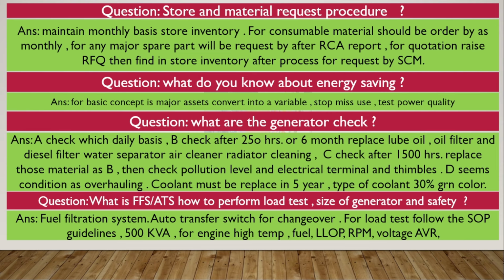What is FFS, ATS, how to perform a load test, the size of the generator, and safety? FFS is the fuel filtration system. ATS is the auto transfer switch, used for changeover. For a load test, follow the SOP guidelines. You can tell about your generator size, like 510 kVA, 100 kVA, 200 kVA, whatever you know. For engine-side safety: high temperature, fuel level, low lube oil pressure, RPM safety, and voltage AVR as well.